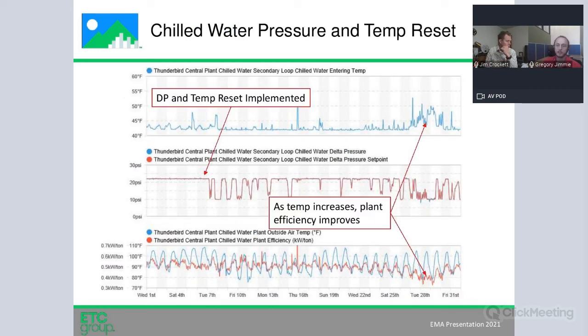So here's an example in which we implemented a differential pressure reset as well as a temperature reset. One really good way to go about doing this, that we've had a lot of success with, is to see how they interact with one another. For the differential pressure, typically we would like to respond first to allow the system to get more flow to those coils, and then the temperature has a longer lag time. So that's generally the second step you can go after.